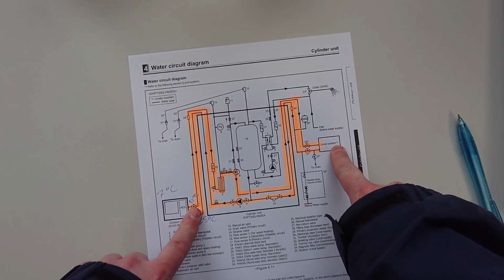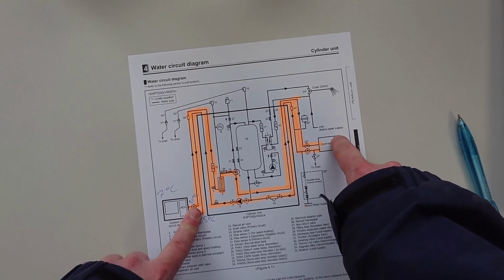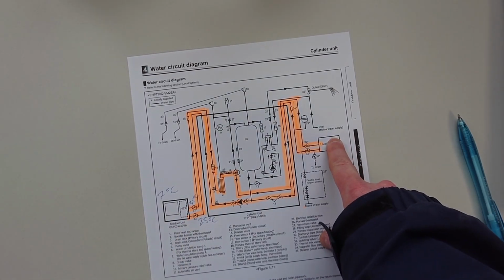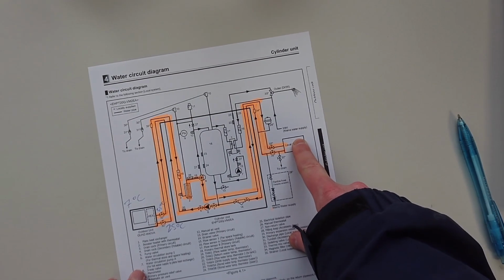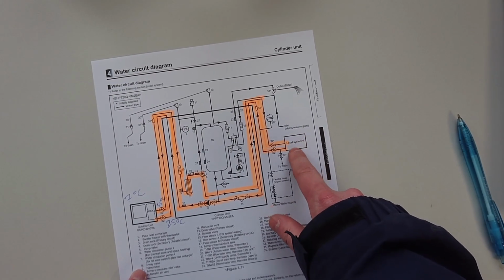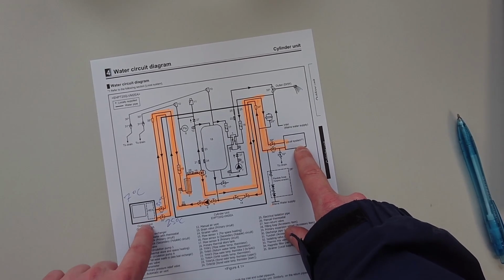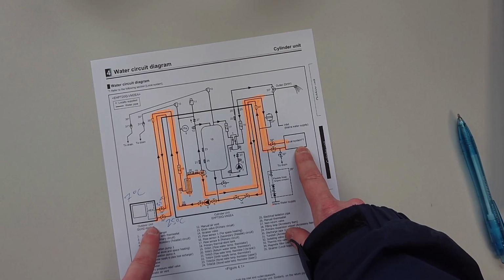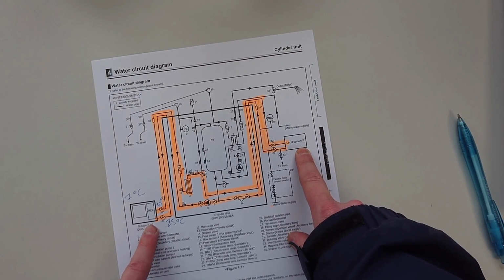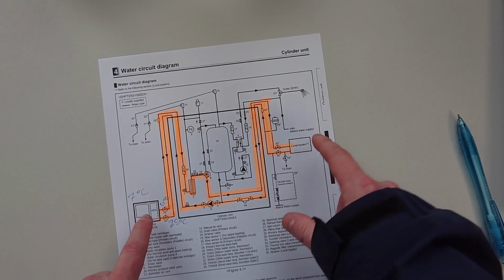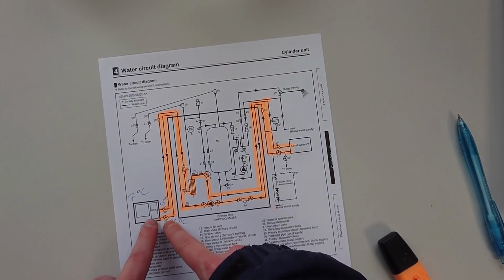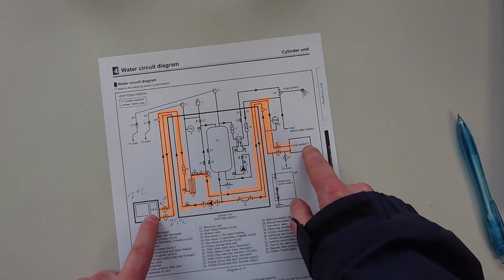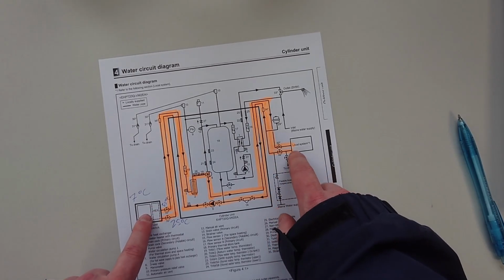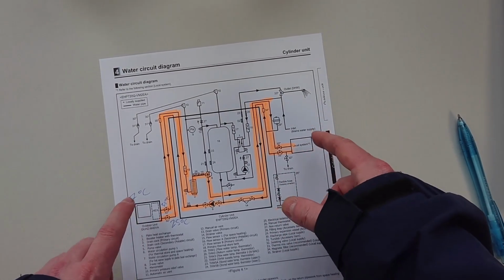But this bit over here is the bit that depends on how good your install is. And if your install maybe isn't the best for whatever reason, because it's not quite as simple as just changing a boiler, this could be where you're actually losing all the COP, and it might be nothing to do with the heat pump part of it. It probably is working fine. It's just a fridge, and they all work, or it's a heat pump. But fridges are all heat pumps, vice versa. A heat pump is anything that moves heat. They all work the same for the same condition, so any difference between one and the other is always down to this install part, which unfortunately people don't want to hear, but it is.